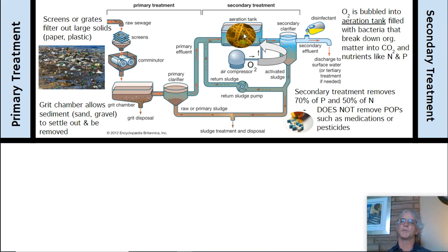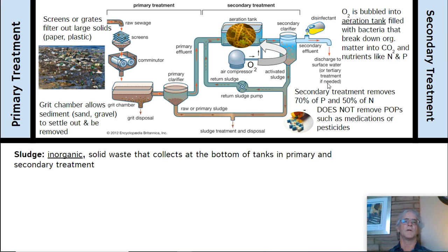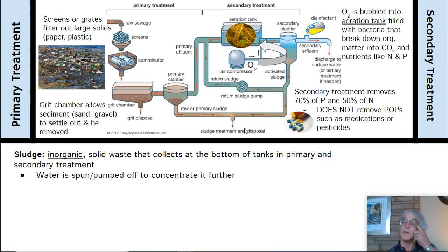Secondary treatment removes 70% of phosphorus and 50% of the nitrogen, but does not remove things like persistent organic pollutants (POPs), medications, or pesticides. The key term here is sludge — the solid waste that collects at the bottom of tanks in primary and secondary treatment. It is put into a centrifuge, spun, and pumped off to concentrate it further.